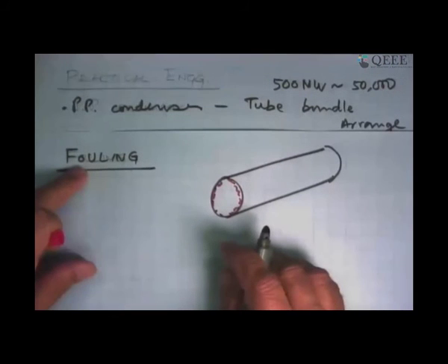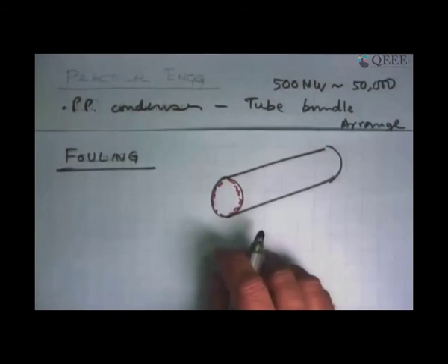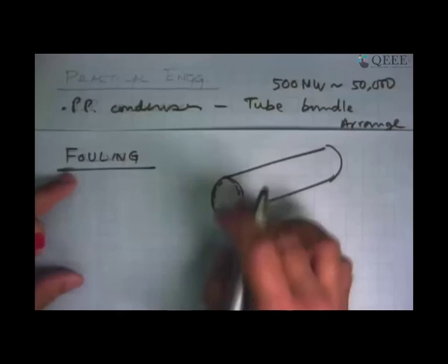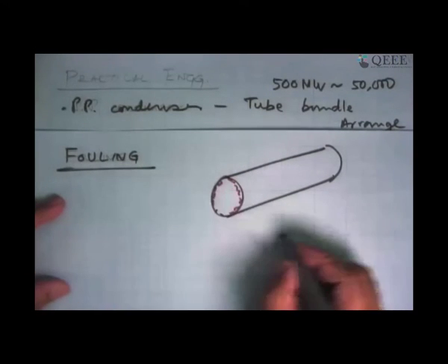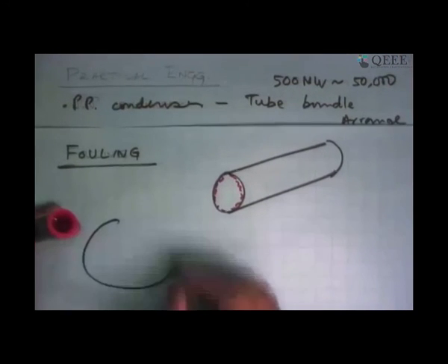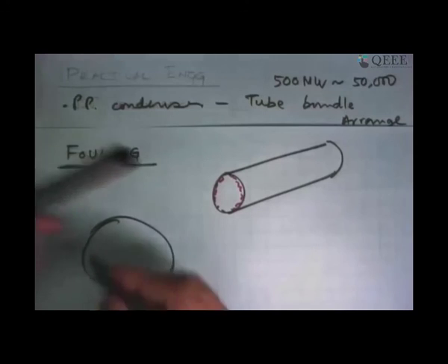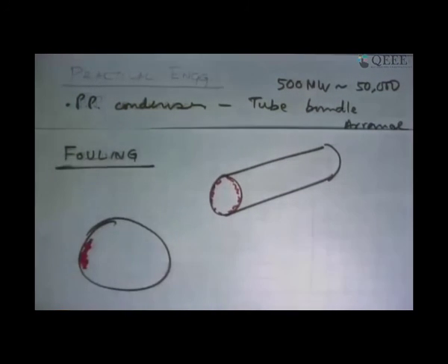That is called fouling. This could be deposits of very fine mud or maybe algae growing on it, something like that. And this introduces an additional conduction resistance. So now the tube surface has got an additional impediment in it. So this was the inside tube surface. We got this fouling thing sitting over here, and inside also and outside also there could be fouling on the steam side.